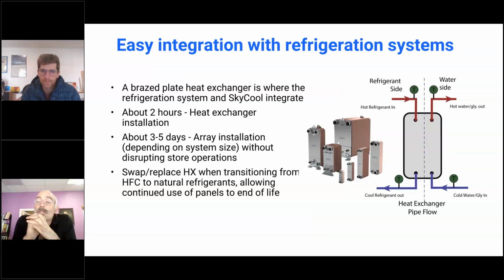Are the pumps start-stop or on VFD, and what is used to control the operation of them? It's a good question. So we have VFD pumps. They're made by Grundfos. They are controlled by sensors that are in the system. So for example, there's an ambient temperature sensor. There's pressure sensors in the system. There's temperature sensors for the fluid. You can see the T icon here. So we're measuring how cold these fluids are, and we control the pump based on all of these sensors.